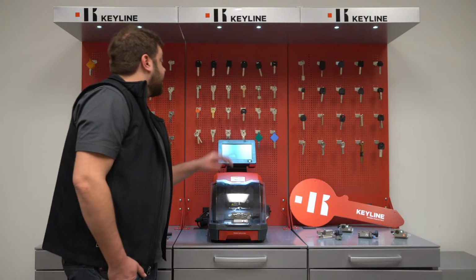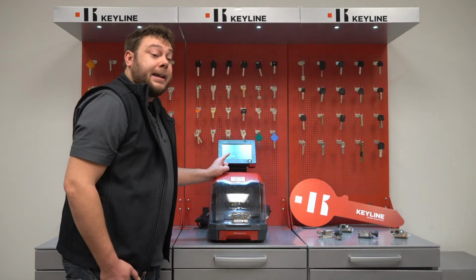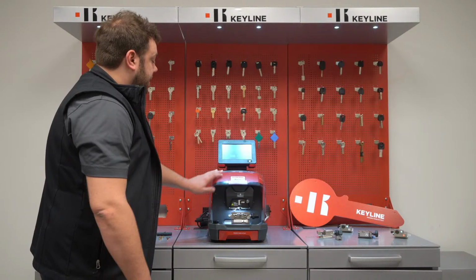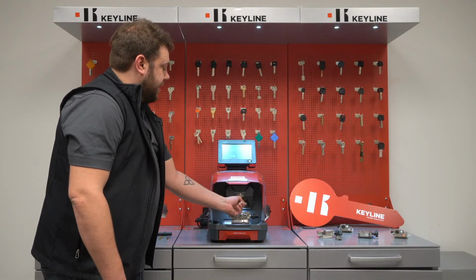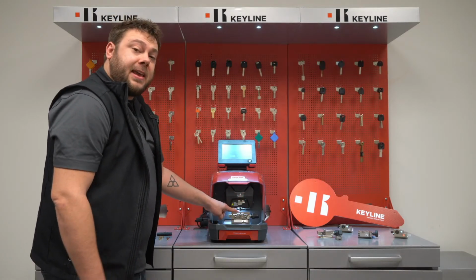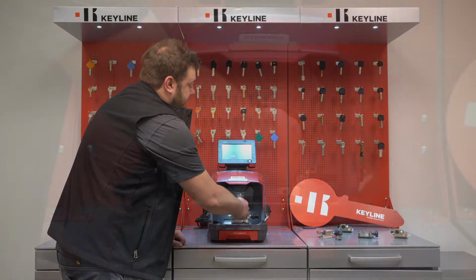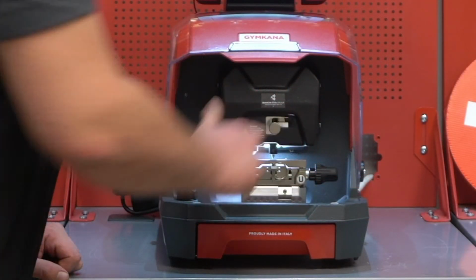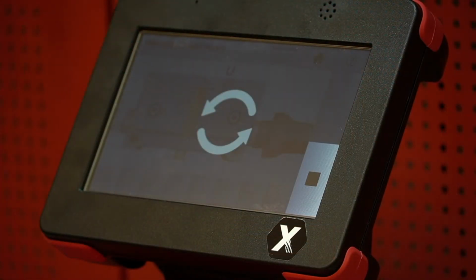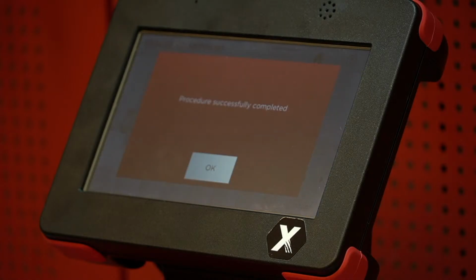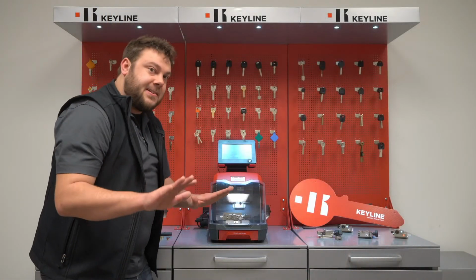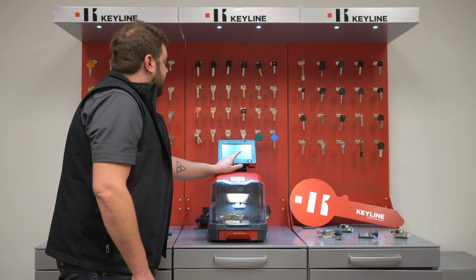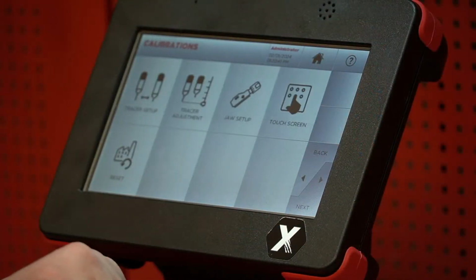All right, now it says, please lower the tracer and lock it in position. Easiest thing in the world, you open it up, you drop the tracer knob down so it lands on top of the calibration template, and then you righty-tighty that knob. Once it's locked, you just close the shield, and you press OK. Procedure successfully completed. Our tracer knob is now at the right height, and we shouldn't have to touch it. Now, the important part, we hit OK, hit back, and now we do a jaw setup.